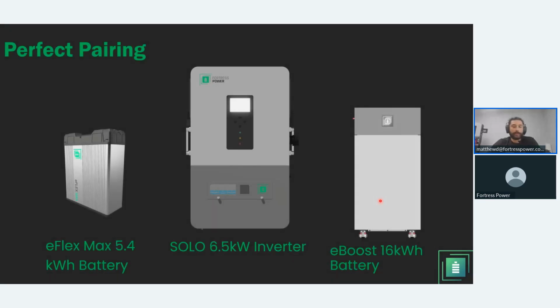All right. So like I said before, this inverter pairs perfectly with the eFlex Max 5.4 kilowatt hours. We do recommend having a minimum of 2, since the battery charge is 140 and the maximum charging and discharging amps of the eFlex Max is 100 amps continuous. So 2 of those would be perfect with the Solo 6.5, and that should cover most of your single home, 1-bedroom home, maybe apartment or small home.